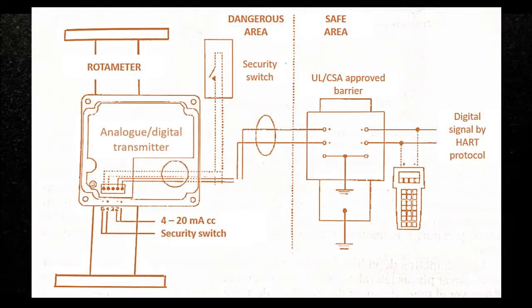The analog-digital transmitter is hybrid, because it uses the HART protocol, which allows sending the 4 to 20 mA DC analog signal and the digital signal through the same pair of wires as the electronic analog transmitter. If you want to know more about the HART protocol and the types of transmitters, I will leave my videos in the eye for you to check.